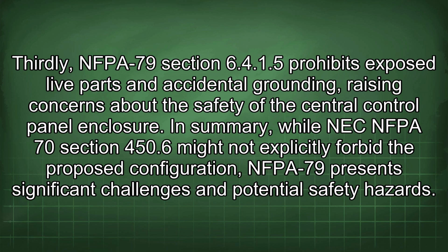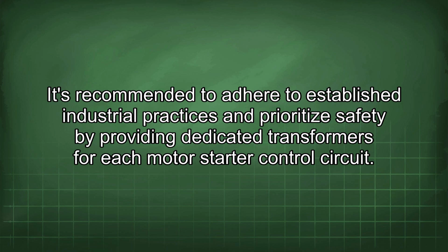In summary, while NEC NFPA 70 Section 450.6 might not explicitly forbid the proposed configuration, NFPA 79 presents significant challenges and potential safety hazards. It's recommended to adhere to established industrial practices and prioritize safety by providing dedicated transformers for each motor starter control circuit.